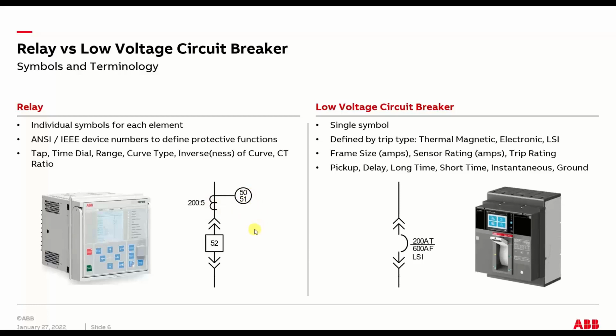But there's a unique utilization of these ANSI device codes for relaying, for medium voltage, that don't necessarily convert over to or are used in the low voltage. So in other words, these two numbers, 50-51, are instantaneous and time overcurrent protection as defined in the standard. The device 52 is the actual circuit breaker itself. This 200 to 5 is just the ratio of a CT. And then the equivalent for a low voltage circuit breaker is its trip characteristics. In this case, it's electronic, so it's LSI: long, short, instantaneous. And then its sensor and frame ratio: 200 amp trip or 200 amp sensor plug, and then 600 amp frame.